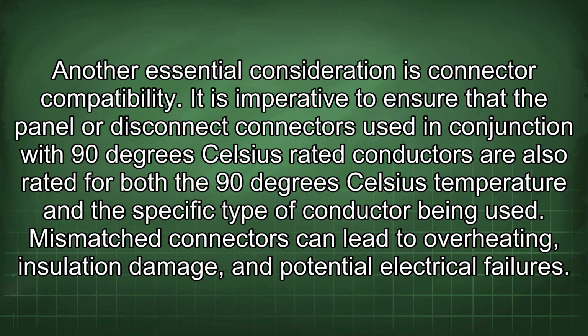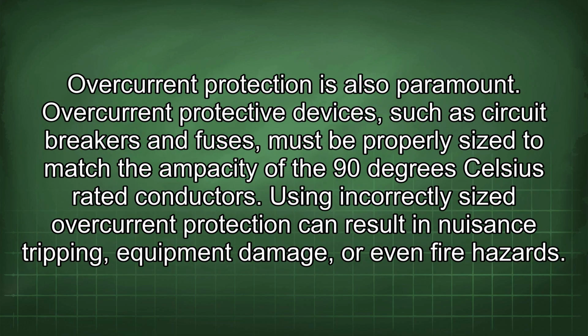Another essential consideration is connector compatibility. It is imperative to ensure that the panel or disconnect connectors used in conjunction with 90 degrees Celsius rated conductors are also rated for both the 90 degrees Celsius temperature and the specific type of conductor being used. Mismatched connectors can lead to overheating, insulation damage, and potential electrical failures. Overcurrent protection is also paramount. Overcurrent protective devices, such as circuit breakers and fuses, must be properly sized to match the ampacity of the 90 degrees Celsius rated conductors. Using incorrectly sized overcurrent protection can result in nuisance tripping, equipment damage, or even fire hazards.